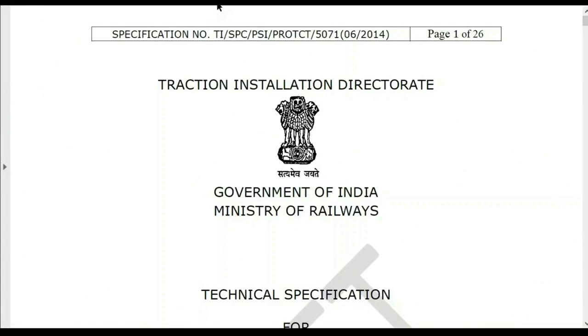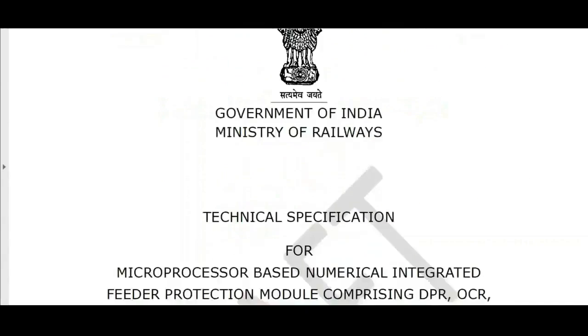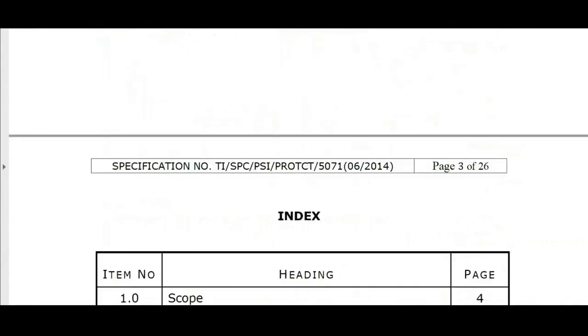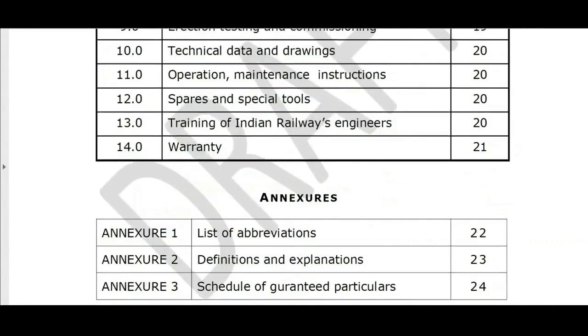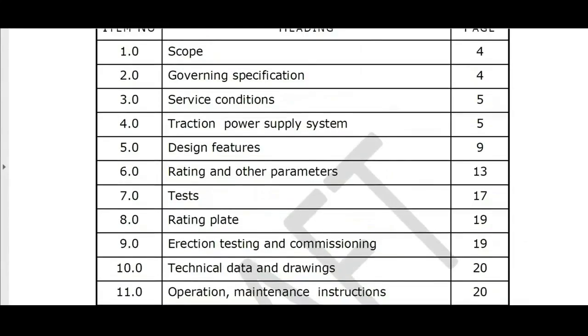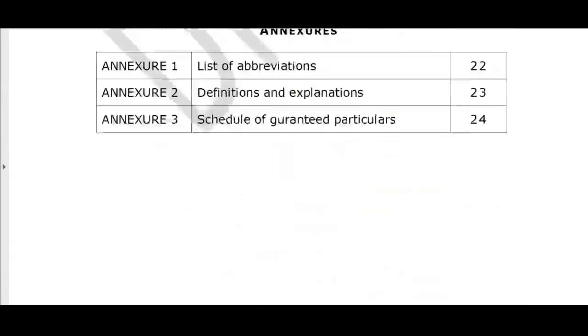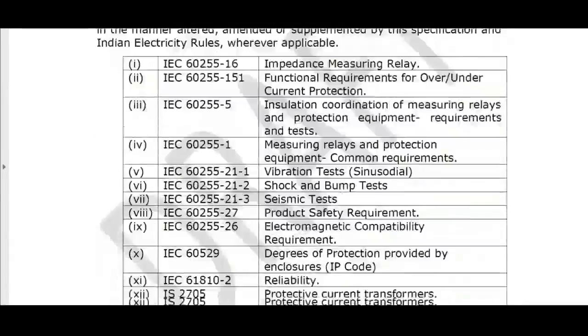This 26-page RDSO specification, maybe you have the latest spec also, you can use it, but the fundamentals never change. The spec normally talks about, when you are buying an equipment, what should be the specification of that equipment. So there will be some advancements in every new specification. However, the fundamental protection system is always maintained. So when you move into the specification, it defines the list of protection functions required. So let us go through it one by one.